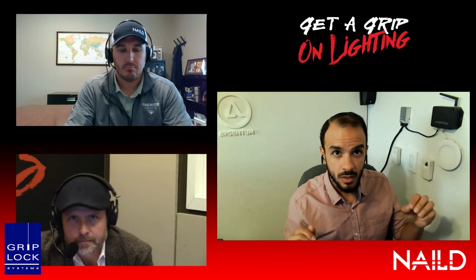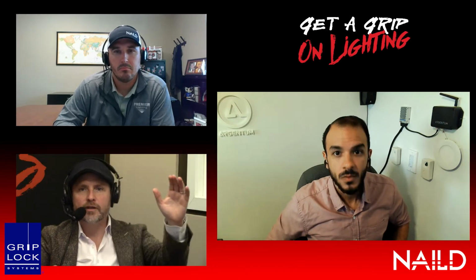What's not safe for DC is mechanical contact. So AC breakers are no good for direct current. You wouldn't be able to use those for direct current. And if you look at a properly marked breaker or the datasheet, the DC rating will be much, much lower. Same with a mechanical wall switch. So as long as you're addressing the two endpoints, the light fixture and the panel, the infrastructure can stay the same.